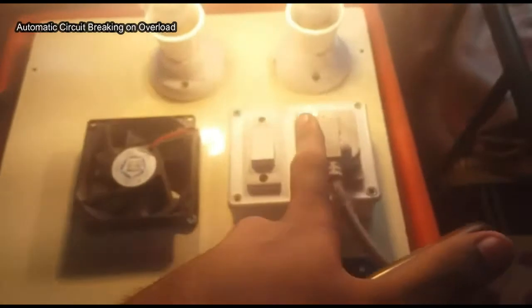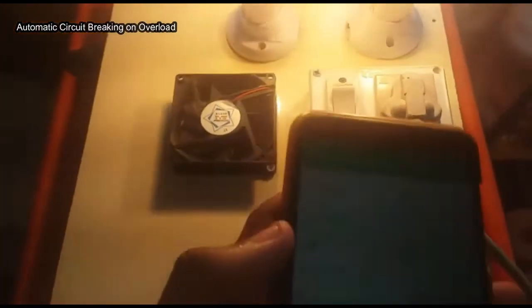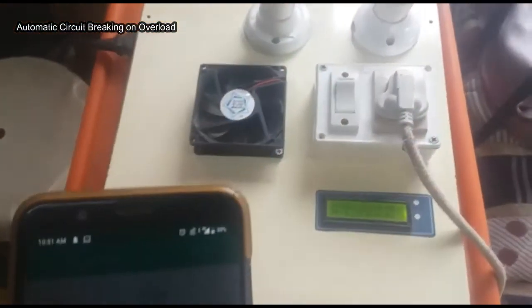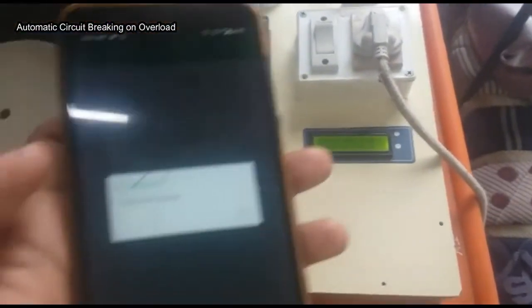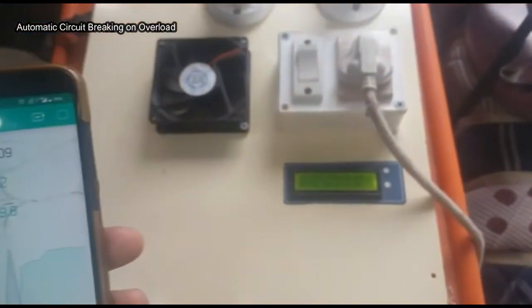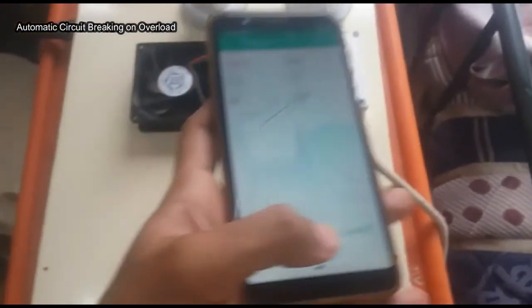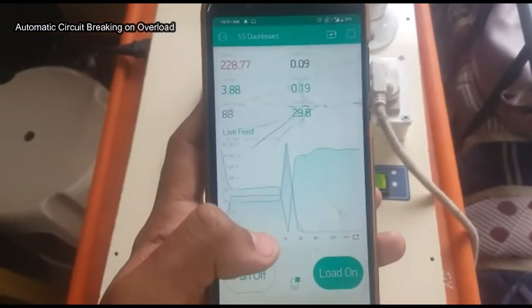Automatic circuit breaking on overload. Every time, the measured current is compared to a preset value, and if the measured current is higher than the preset value, here it's 5 amp as it is the sensor's recommended maximum value, beyond which error offset increases or the sensor breaks down, the relay is automatically activated and it breaks the circuit.